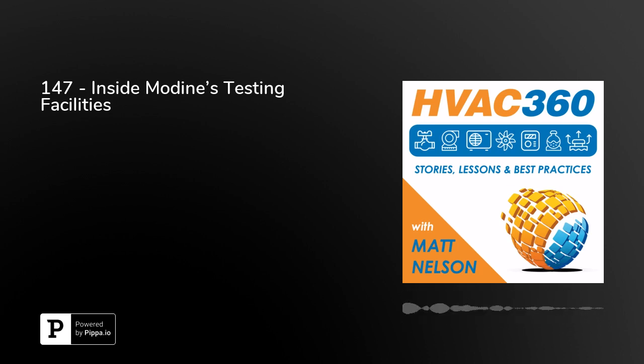So when you talk about the tonnage of a room, what does that mean? Tons of refrigeration. For example, the large wind tunnel has a 520-ton chiller that services that room. So we can take quite a bit of heat out of there. That's how we get down to negative 20 and handle large heat loads. And for the rooftop unit, we can handle up to 90 tons, so the heat coming off of the unit, the condensers, the compressors, electronics, that kind of thing.